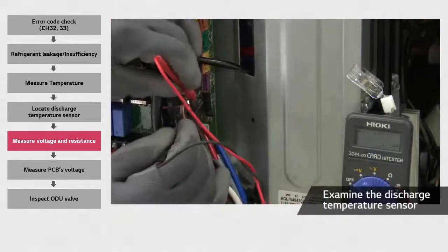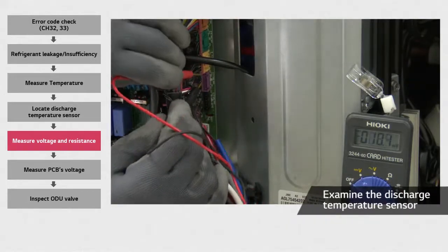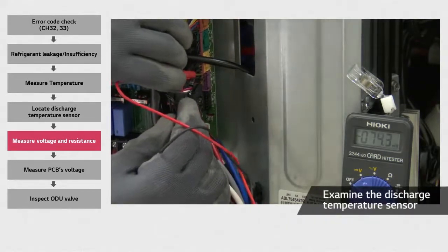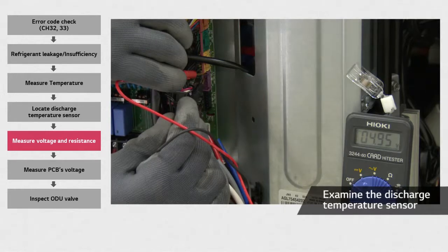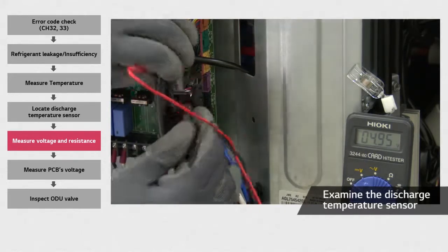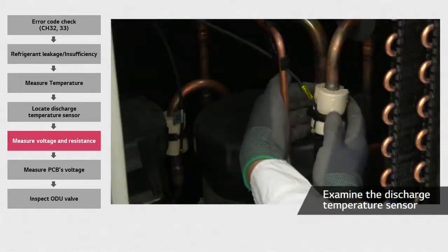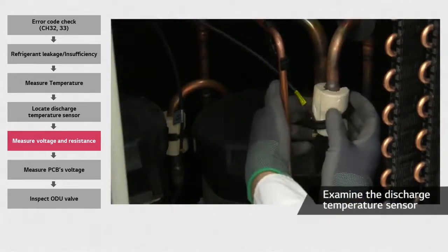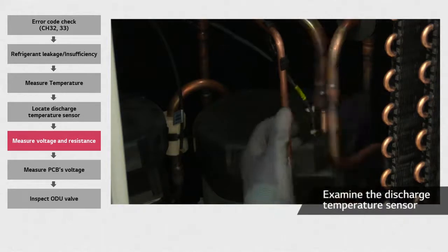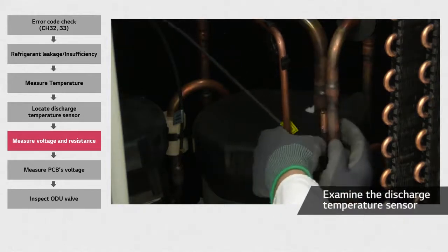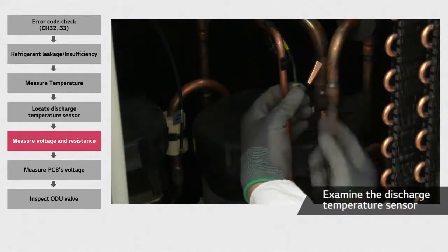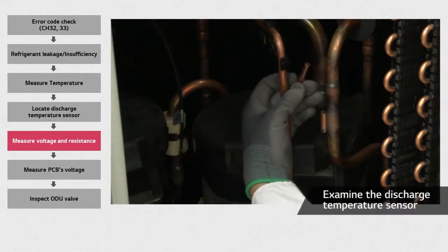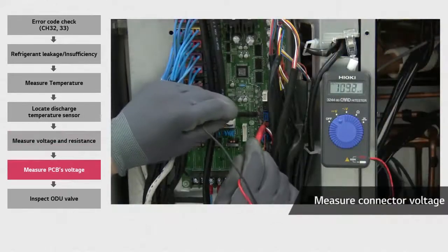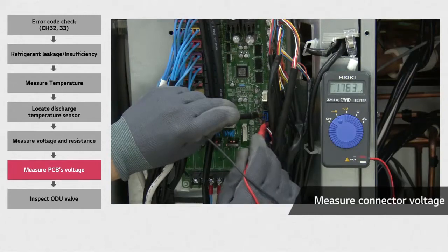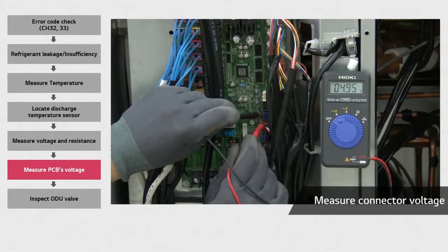Inspect the voltage of the discharge temperature sensor. Check the discharge temperature sensor connector DC voltage on the external PCB. The normal reading is 5 volts. If you find any problem with the discharge temperature sensor, replace the broken sensor. To remove the broken sensor, unfasten the clip, remove the insulators, and pull them out. Make sure the DC voltage from the external PCB, the blue connector, is 5 volts.